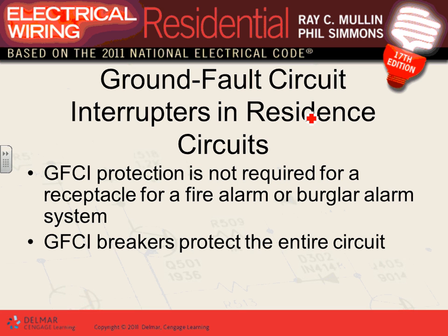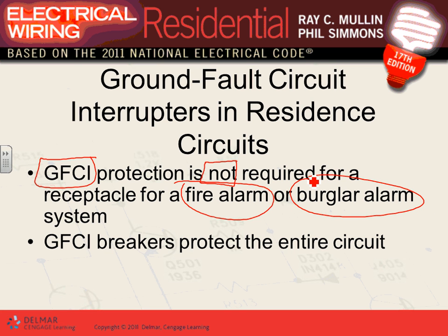Okay, ground fault protection. If you have a dedicated receptacle, it's not required. I want to emphasize the words not required: GFCI is not required for fire alarm as well as burglary alarm. So if you have a fire alarm system in your basement, Karen, and it's plugged into a receptacle in the basement, that receptacle would normally have to be GFCI, except because it's for a burglary alarm and fire alarm, it does not have to be GFCI. Any comments, guys, about the exception for GFCI in a dwelling? Fire alarm and burglar alarm in a basement is an exception.